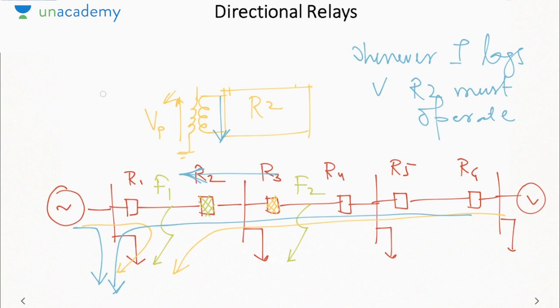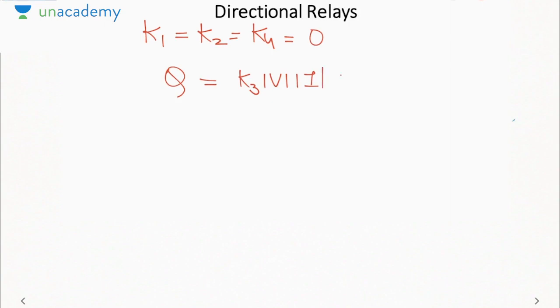So let me show you how we derive the operation of this relay from the universal relay torque equation. Now, in the universal torque equation, what we do is equate K1, K2 and K4 to 0. So what is left is K3 |V||I| cos(theta minus tau). Now you might be wondering how I am reducing the arbitrary terms to 0 in each case. But there is no concept behind it. The thing is that relays are designed in such a manner that such terms will not be present in the construction of the relay. Like a directional relay will not have any overcurrent or over voltage term. That is basically incorporated in the design of the relay.